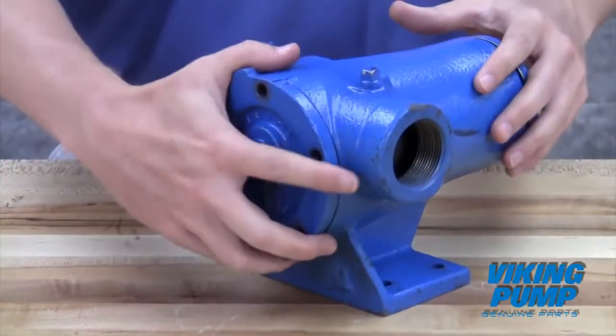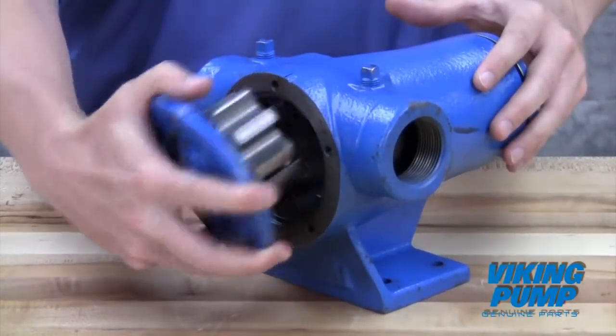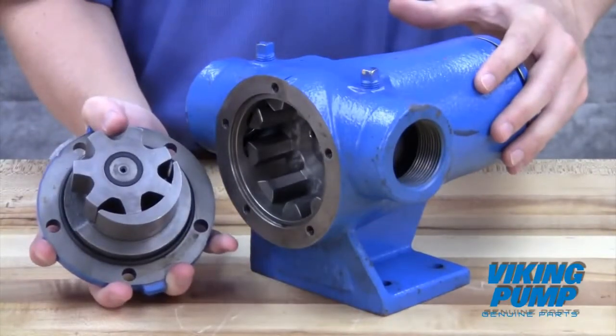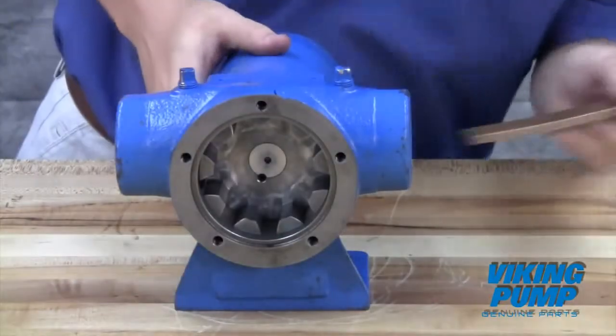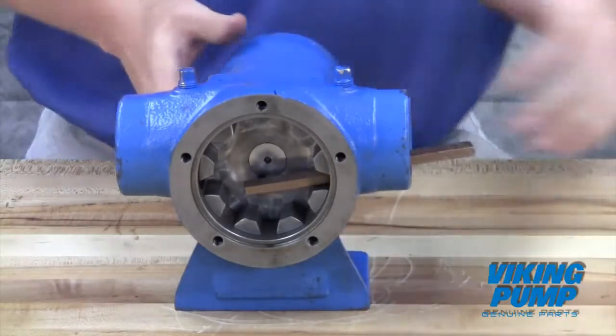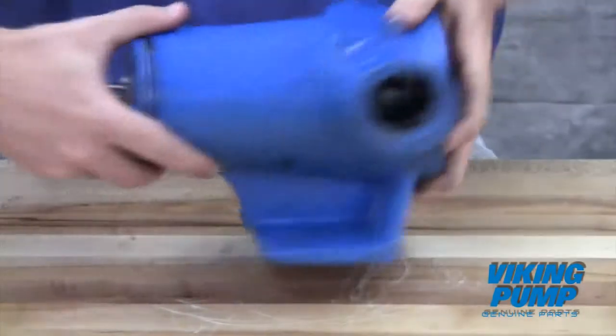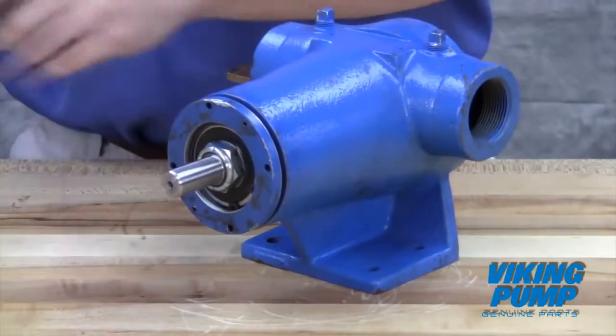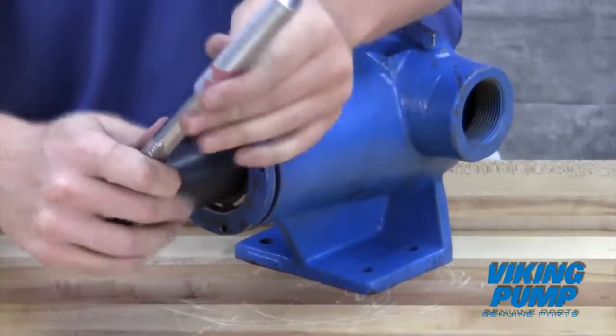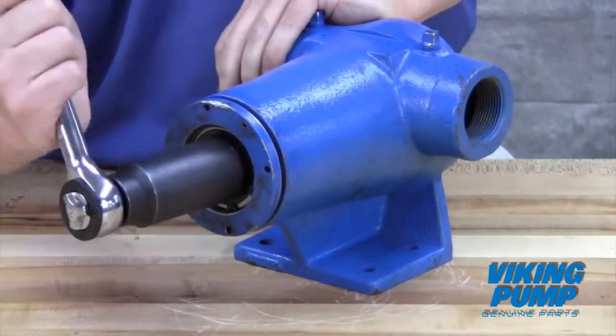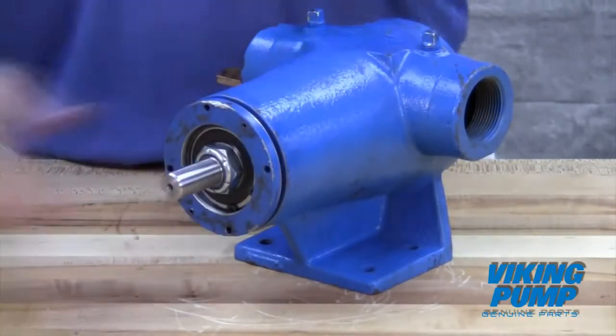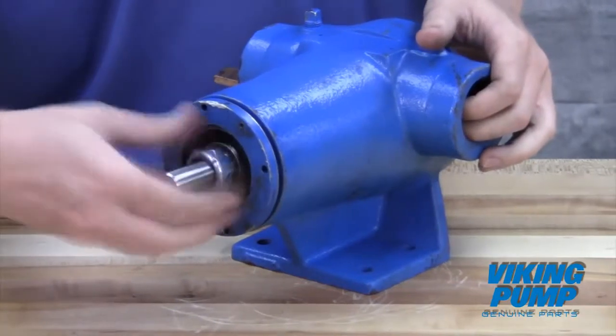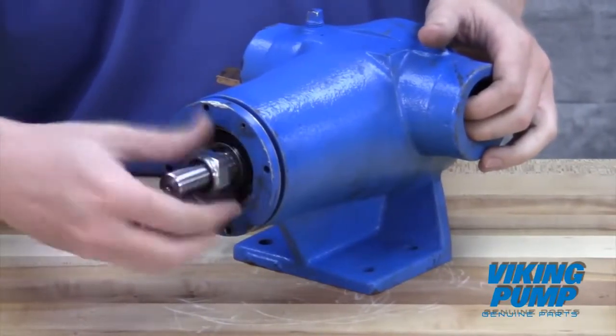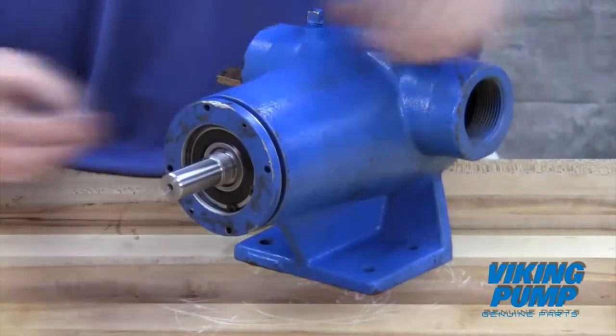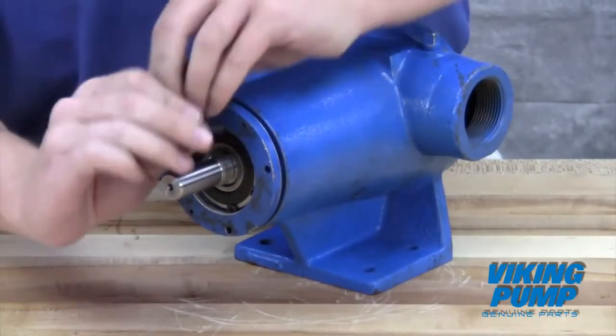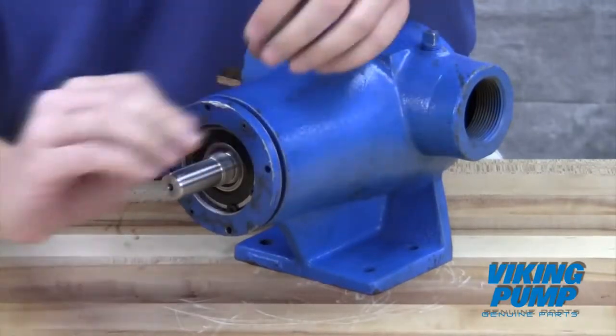Remove the head by tilting it backward to prevent the idler from falling off the idler pin. Insert a brass bar or piece of hardwood in the port opening and between the rotor teeth to keep the shaft from turning. Turn the lock nut counterclockwise and remove the lock nut. Loosen the bearing housing set screws and remove the bearing housing by turning it counterclockwise.